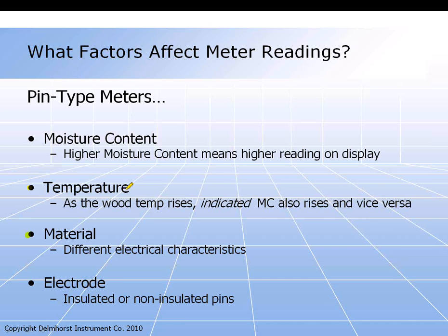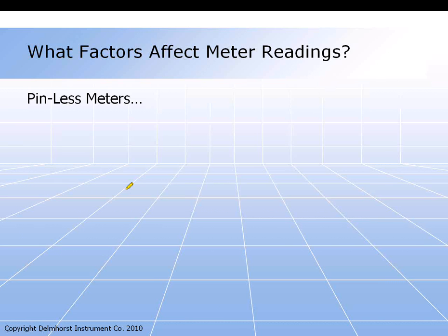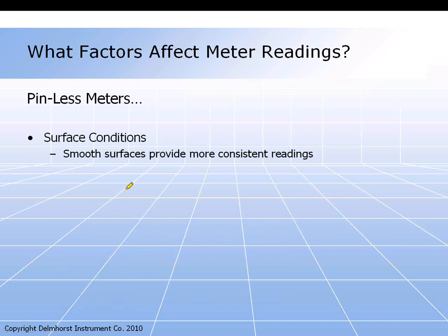So just going back and summarizing, these 4 things are things that affect your readings. It doesn't mean the meter is more or less accurate. For example, Tech Check is not less accurate than a Navigator Pro. It's just that when you're dealing with different temperatures and materials, you need to make a manual correction versus the meter correcting for you.